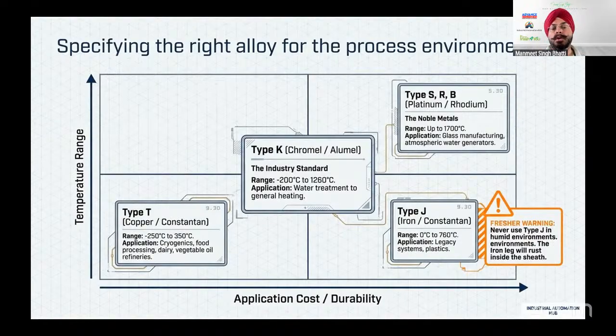But why are they called K, why are they called T, why are they called S, R, B, J? There is a reason behind that: all these are classifications. Now, if you go for a T-type thermocouple, it's copper and constantan. These are the two metals or alloys being used, and the range is minus 250 degrees to 350 degrees. So if you have any cryogenic or freezing applications, we can move into the type T sensors. So it is defined on the ranges first.